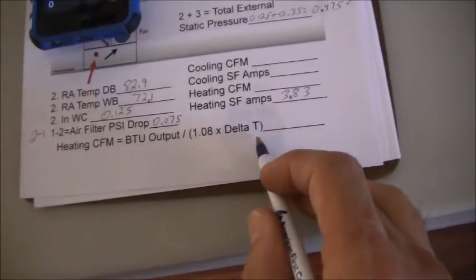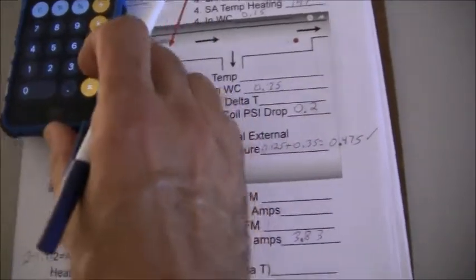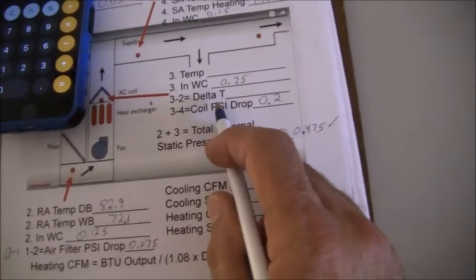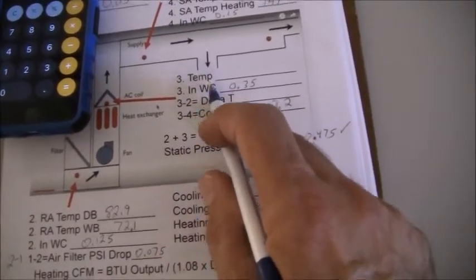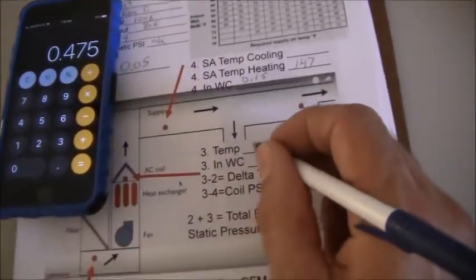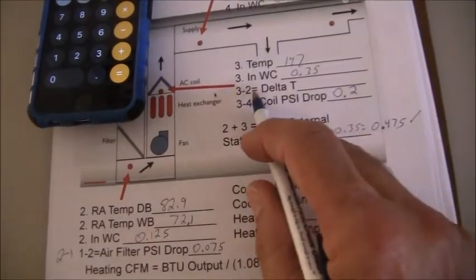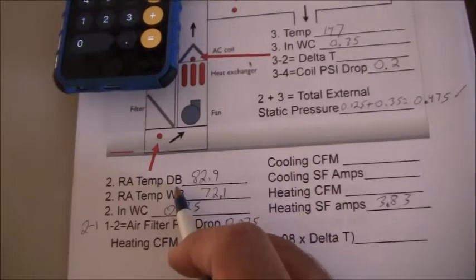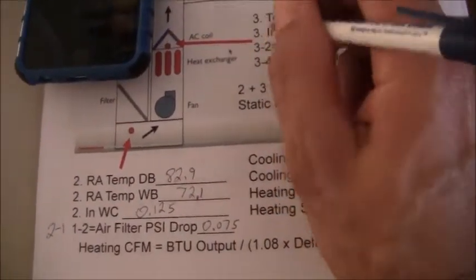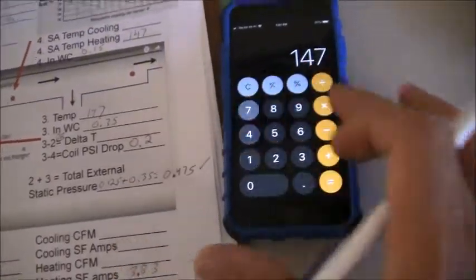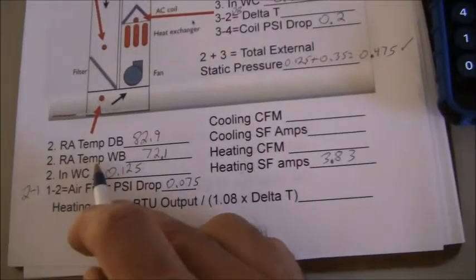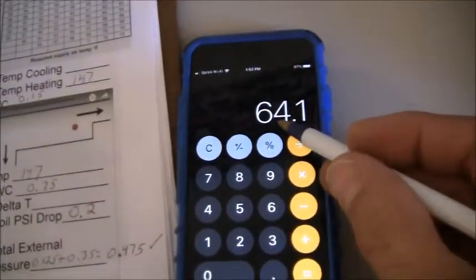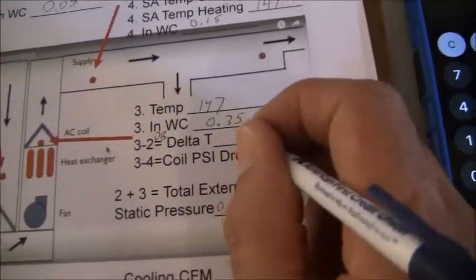So what is the delta T? The delta T is 3 minus 2. So 3 is actually, okay, it's the same. I'm going to put down 3 is the same as this one, 147. So 147 minus 2, that is going to be dry bulb, not wet bulb. So 2 on the dry bulb. So we'll say 3 minus 2 dry bulb is going to be 147 subtract, we're going to take the return air temperature dry bulb 82.9, that equals 64.1. So that delta T is 64.1.